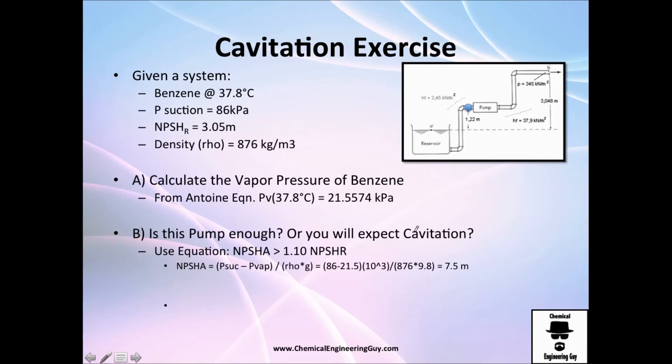Once we have the vapor pressure, recall that we only need to calculate the net positive suction head available and compare it versus the net positive suction head required. By definition, NPSH available is the pressure in the suction line, which we do have, thank God, minus the vapor pressure, which we already calculated. And because I want this in meters, I need to divide by the density and gravity.